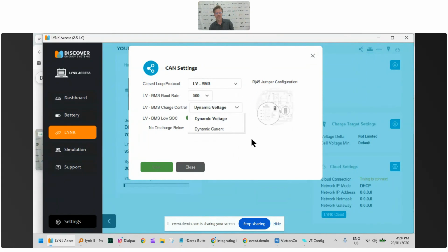What this means is that it can manipulate the inverter's charge rate by changing either the voltage request or the current request. So if you think about Ohm's law, for a fixed amount of resistance, if you reduce one of voltage or current, you're going to reduce the other. So if you drop the voltage request, then the current is going to have to go down as well.